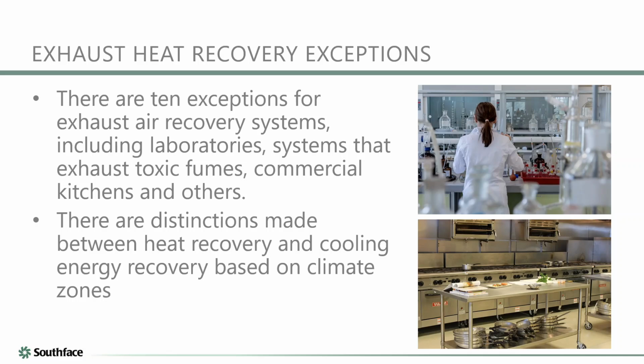As you can imagine, in commercial buildings we have outside air requirements. So we're bringing air into the building, and as you learned from our building science module, that means an equal volume of air is going out of the building someplace else. So when all this air is being pushed into commercial buildings, all this other air has to be pushed out. And that means there are opportunities to do energy recovery from the outgoing airstream. That's basically what this requirement is saying. You should be doing that. There are exceptions because, as you can see here, a commercial cooking environment or a laboratory environment might not be a good option for energy recovery from your exhaust airstream.